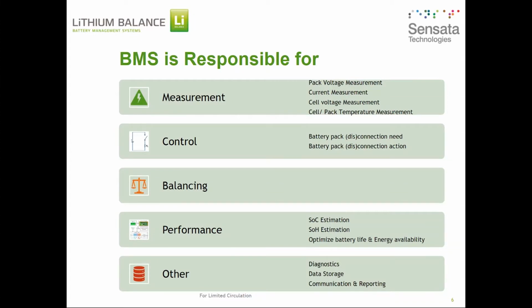The other thing required in control is measurement, which we missed—for current measurement we require a current measurement sensor, which is most of the time external to the BMS. If the PDU is integrated, it will be within the BMS. So current measurement can be done with a shunt, Hall effect sensor, or CAN-based sensor. Every current sensor has its own pros and cons, and the selection will be based on the overall system architecture, end application, sensor manufacturer, its parameters, etc.